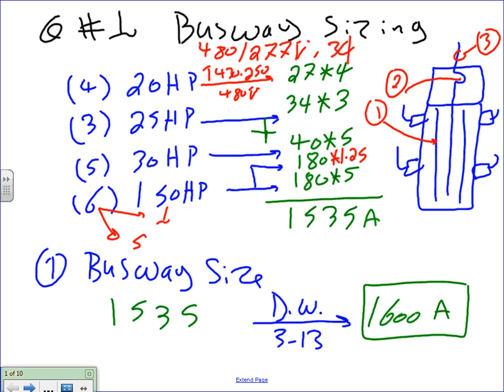But if we were multiplying by all six of them? We can't multiply by all six of them. Yes, it would. You're not supposed to, though. You're supposed to take the largest motor out of the whole system here. I have 10, 15, 18 machines. I need to pick the largest machine and multiply by 1.25. Any question, guys? So the largest machine happened to be one of the 150 motors, only one of them. Any question? Okay, so that's the first thing you're going to do.